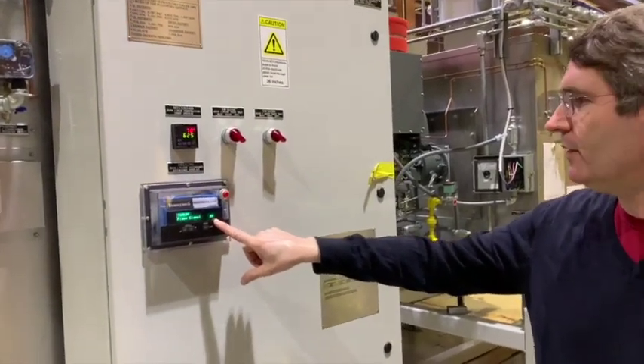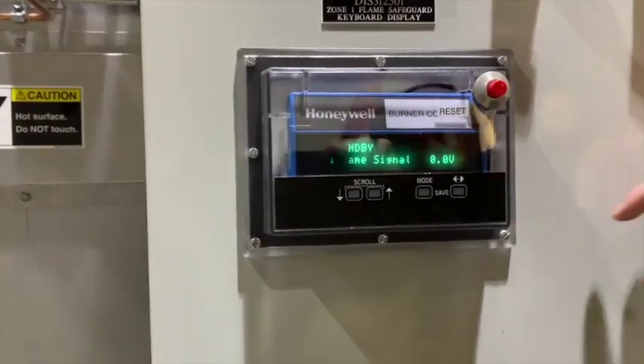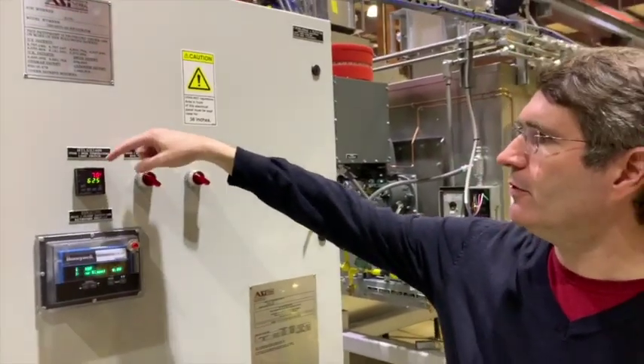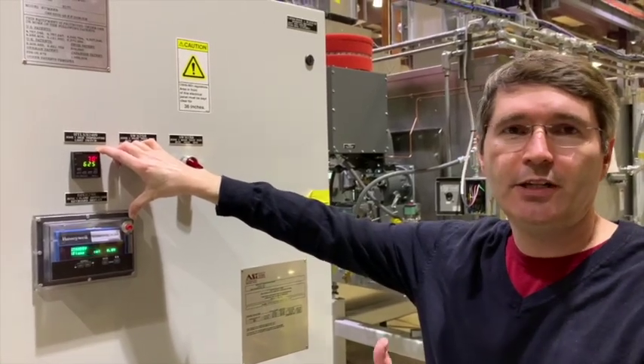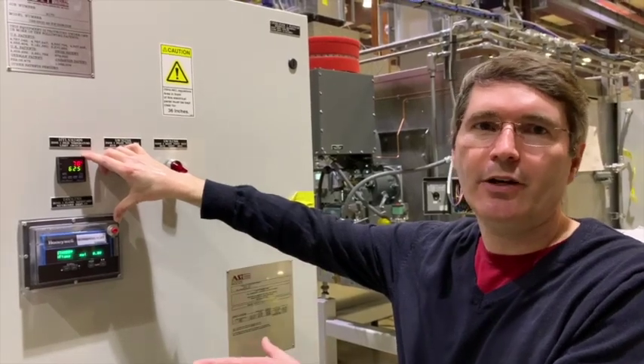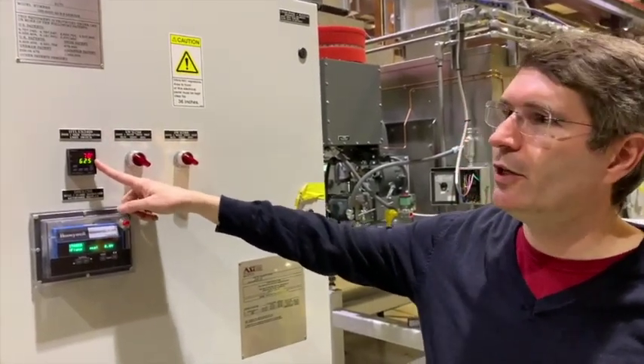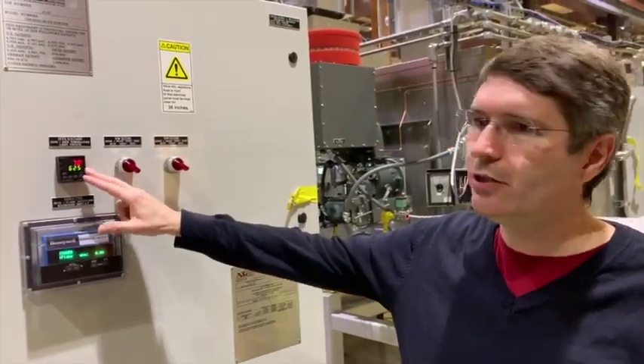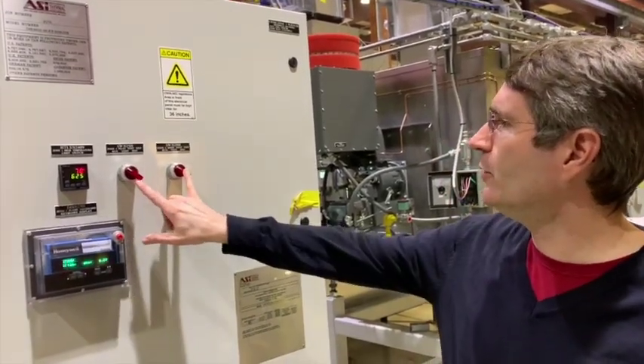They can also go to an RTO for pollution control. We have a flame safeguard in this dryer — this is a Honeywell. It's got a remote interface here; it tells you the strength of the flame signals so you can monitor it for maintenance purposes. We have a high temperature limit switch to make sure that the supply fan is kept safe. This is required by NFPA 86, which is the National Fire Protection Association's code that specifies how dryers are to be built, monitored, and maintained. This is set to 625 degrees.